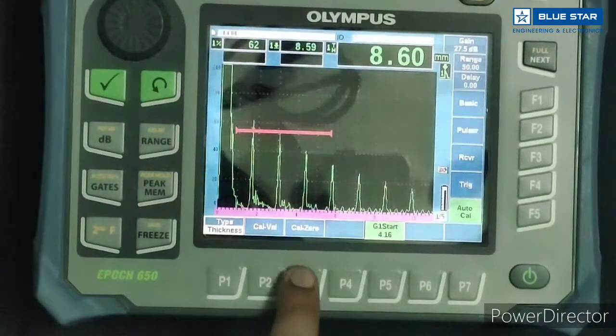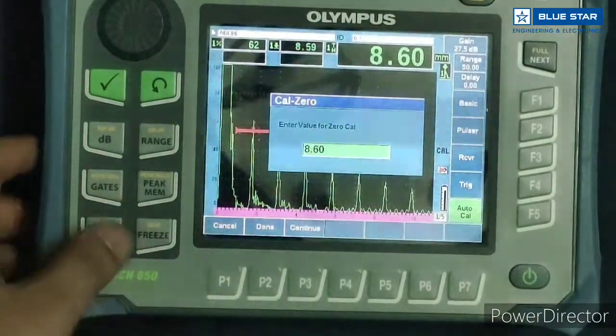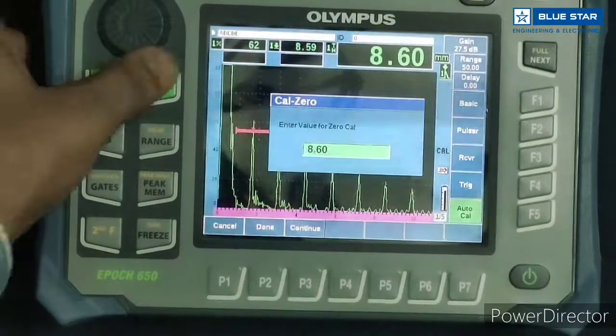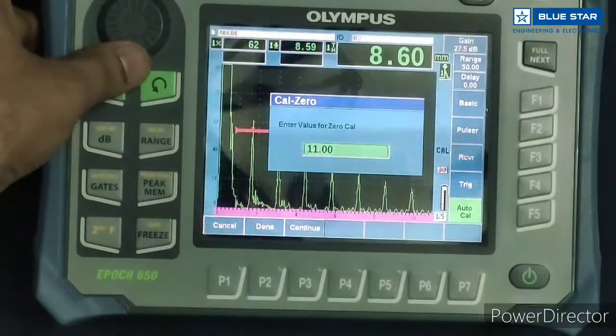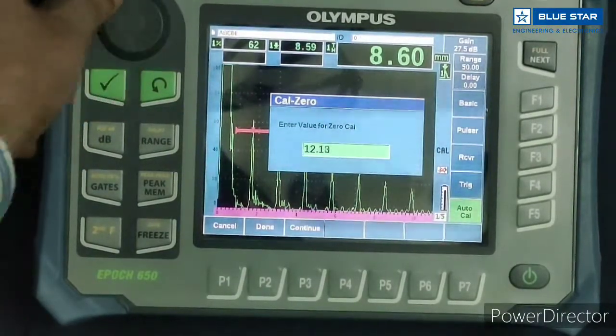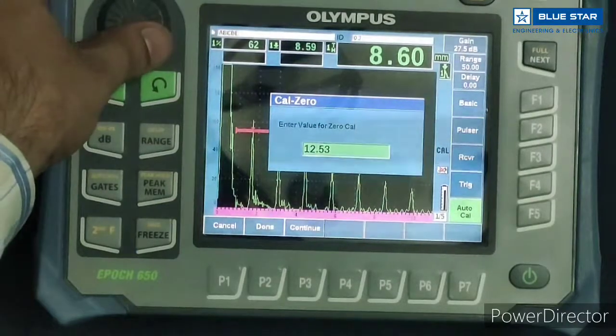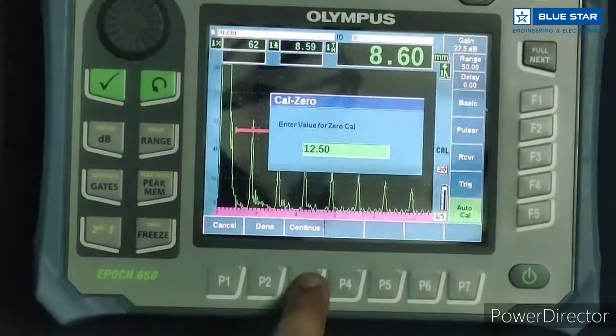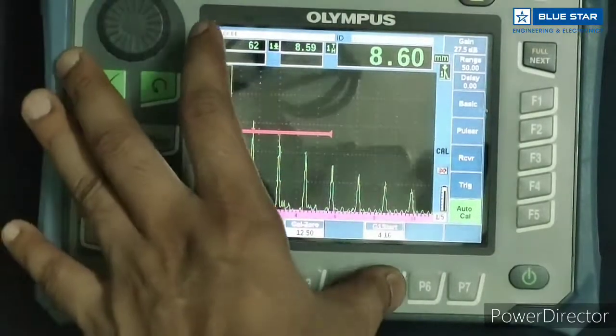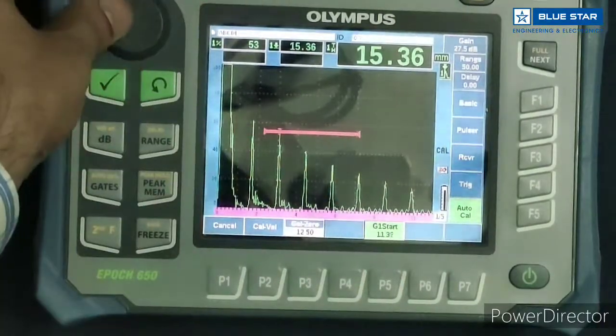Press Cal 0. Thickness of V2 block is 12.5 mm. We need to adjust the value to 12.5 mm. By using this OK key, we can select the coarse step and fine step. 12.5 mm, press continue. Then go to second backwall indication.